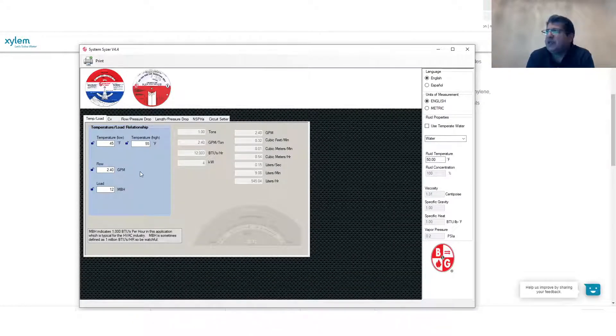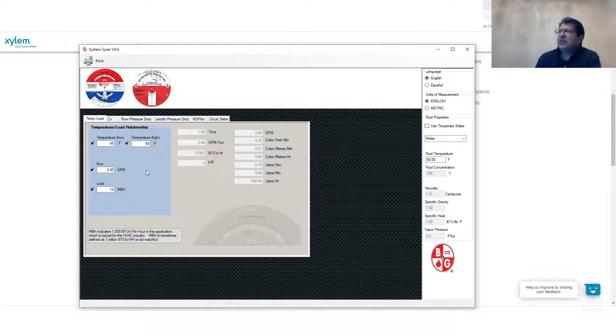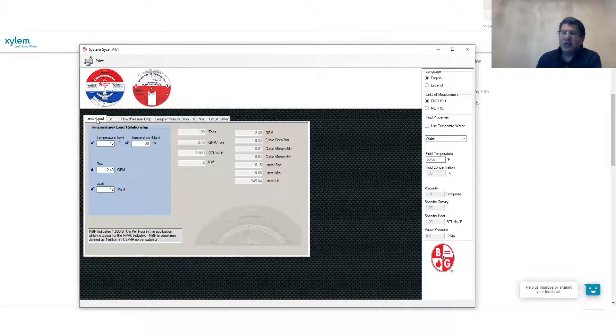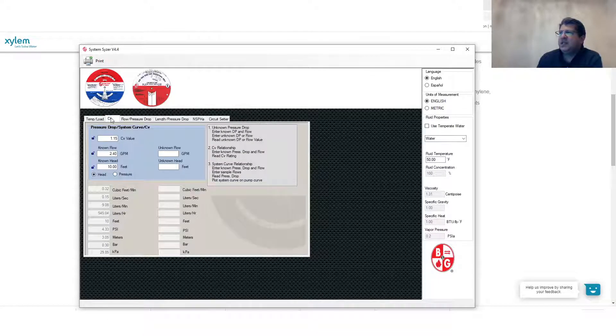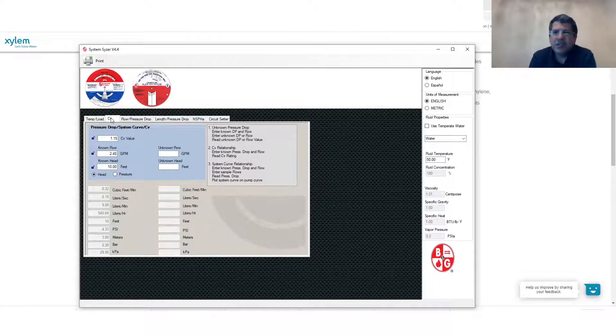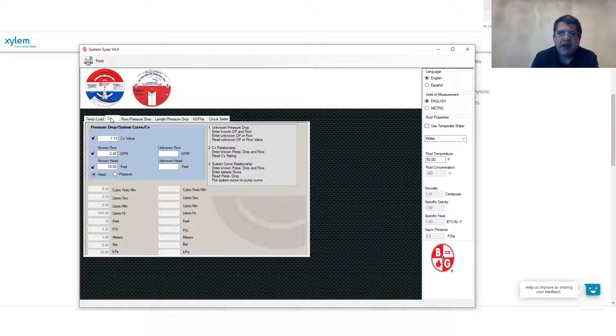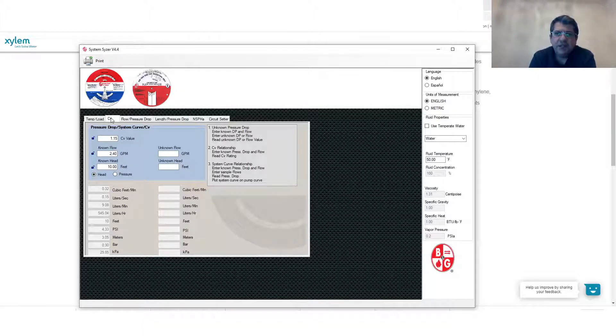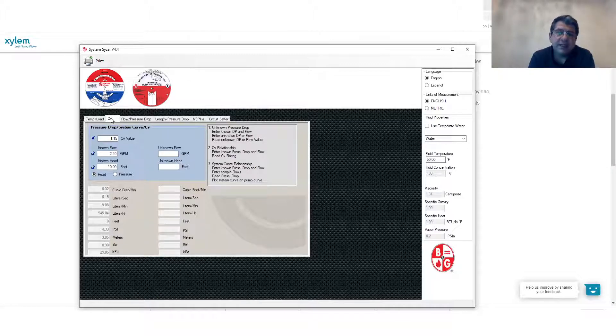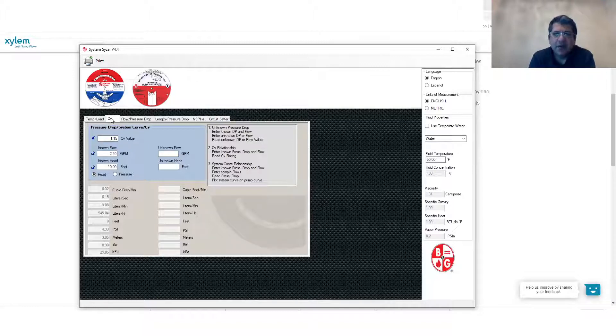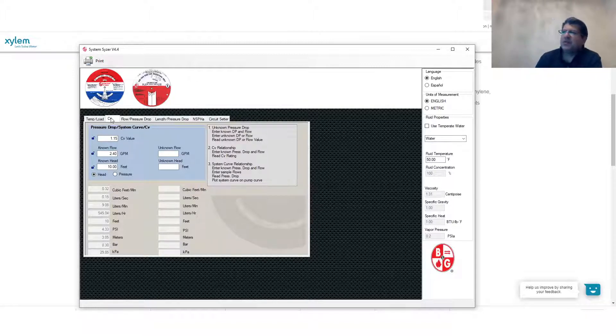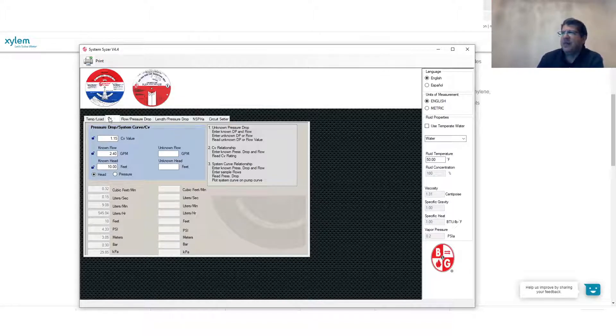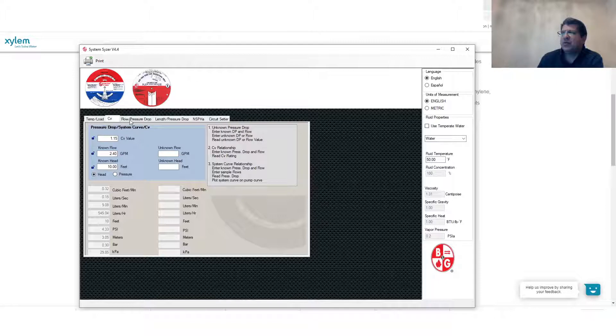When you run this tool you have to look at the top of the menu. There are temperature and load calculations. You have CV or constant coefficient. If you remember we have the constant coefficient of the valve which was a relationship between the pressure drop across a valve and also in a system as a whole and also the flow rate in that system. So you could calculate the CV and it can be done automatically with this very useful tool.